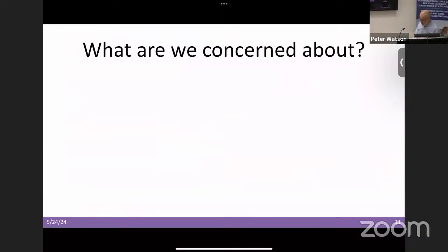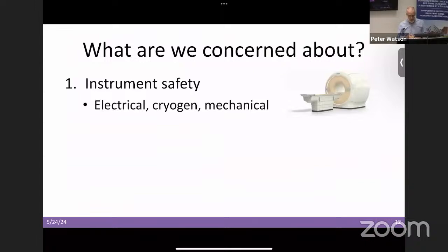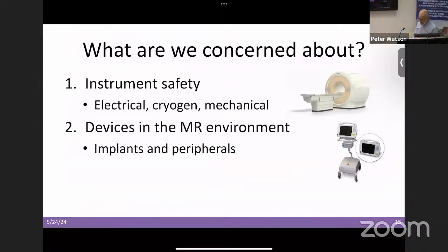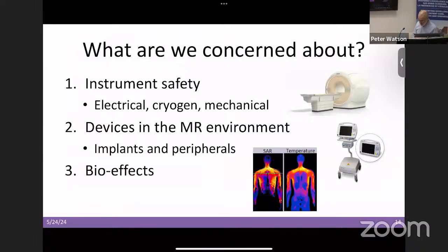So what are we concerned about when it comes to MR safety? You've already gotten some hints because of what I've talked about already. Well, first of all, which I haven't mentioned, is instrument safety. There actually are guidelines that are applied to medical devices, including MR scanners, that ensure that electrically and mechanically, these are safe devices to be around, to lay down on and to submit yourself to an MR examination. We're also concerned with devices in the MR environment. So if you need to have an electrocardiograph while you're in there, or you need to have some kind of an injection coming from a power injector, these peripherals have to be checked out for the MR environment. You may have an implant, that also has to be checked out before it goes into the MR environment.